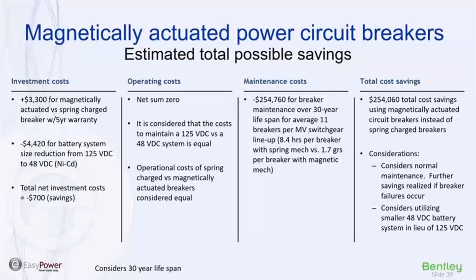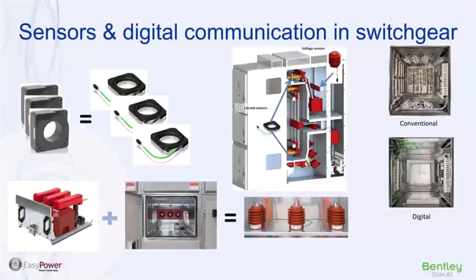Then look at another set of technologies. So current and voltage sensors are using digital communication, right? We have seen when you use these technologies, you can actually reduce the footprint of your switchgear, and not only that, you can massively reduce the amount of wiring that is involved in that switchgear, right? And then you combine that with your digital communication technologies, you basically have total awareness of the state of your switchgear at any point in time. Okay. Again, what we have seen, once you reduce your footprint, you're basically going to save on your upfront investment, the cost of the gear as well as the cost of building.